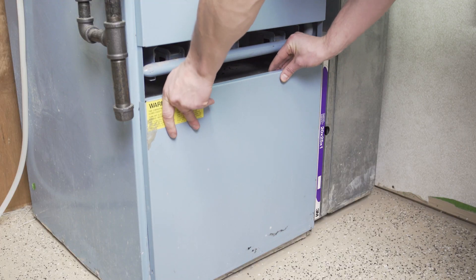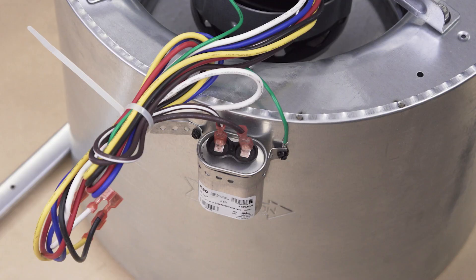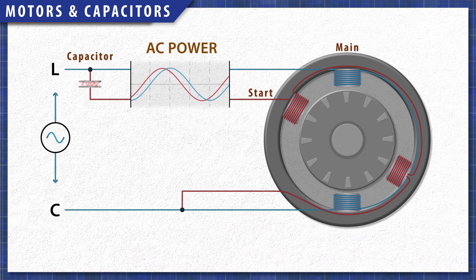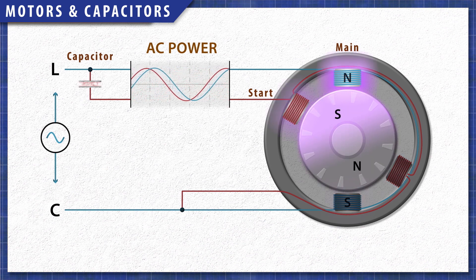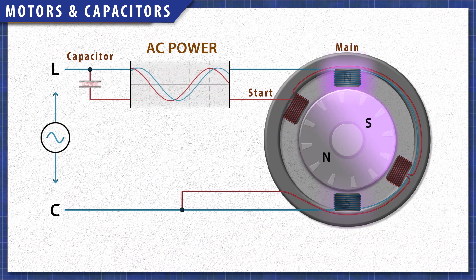Larger motors, like those used in furnaces, air conditioners, and pumps, need a capacitor to start and operate the motor. Capacitors store electrical energy, but can weaken over time, so it's best to check the capacitor first before replacing the motor.